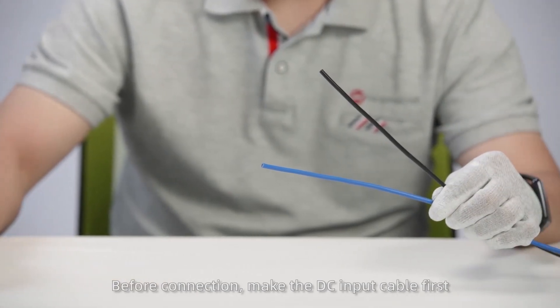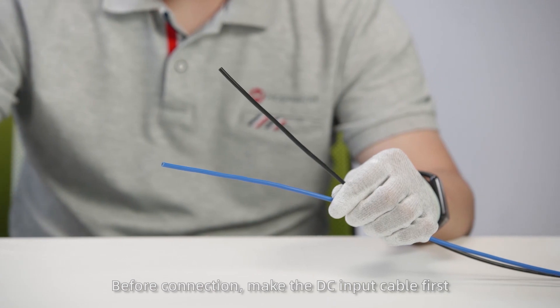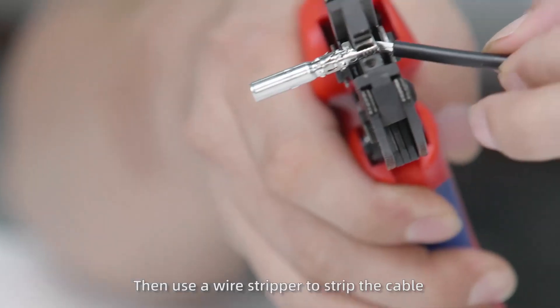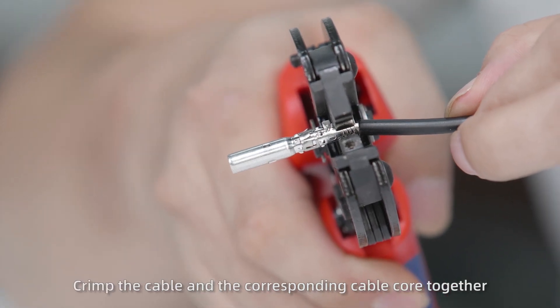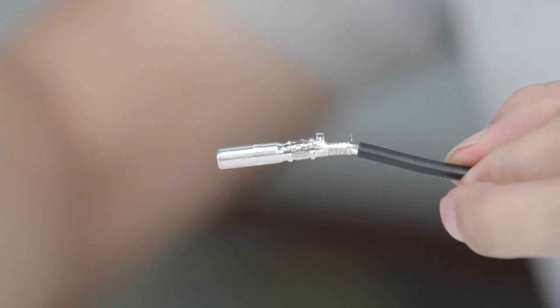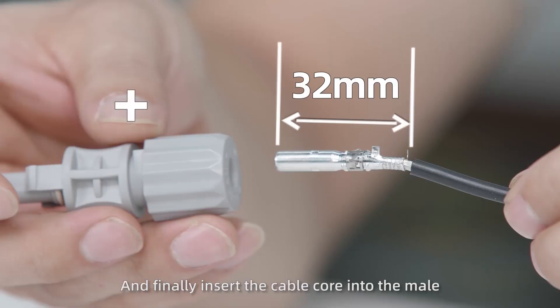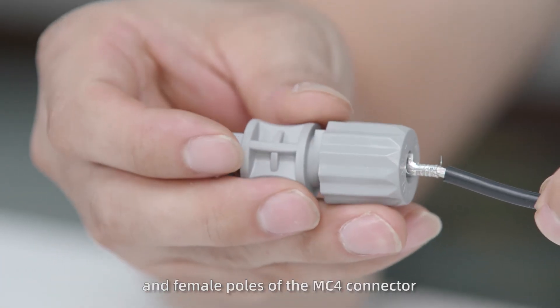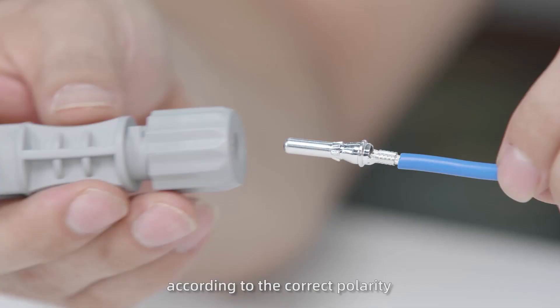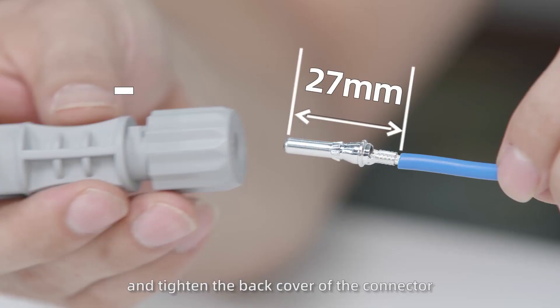Finally, connect cables on the DC side. Before connection, make the DC input cable first. Confirm the positive and negative poles of the input cable, then use a wire stripper to strip the cable. Crimp the cable and the corresponding cable core together, and finally insert the cable core into the male and female poles of the MC4 connector according to the correct polarity, and tighten the back cover of the connector.